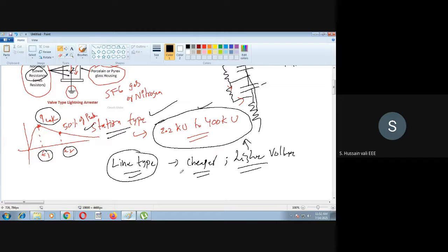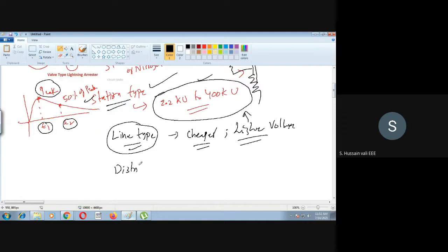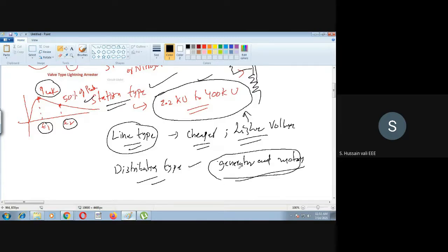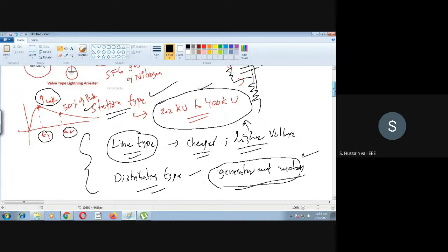Now the third type is distribution type. These are the three types of valve lightning arrestors: station type, line type, and distribution type. This is mainly used in protecting generators and motors, and also generally for protection on the distribution side. So you call this the distribution type valve lightning arrestor, generally used for protection of generators and motors. These are the three types of valve type lightning arrestors.